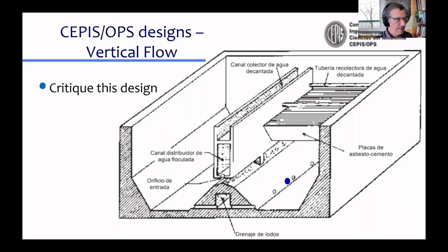And I'm betting you're thinking that's not a good idea. And you are right. It's not a good idea. I think this design was made before, I was looking at their manual this morning, and they have a picture of plastic plate settlers that failed because they got brittle, which goes to another insight that Agua Clara has had, and that is that all water treatment plants should be under roof to protect the system from sunshine.